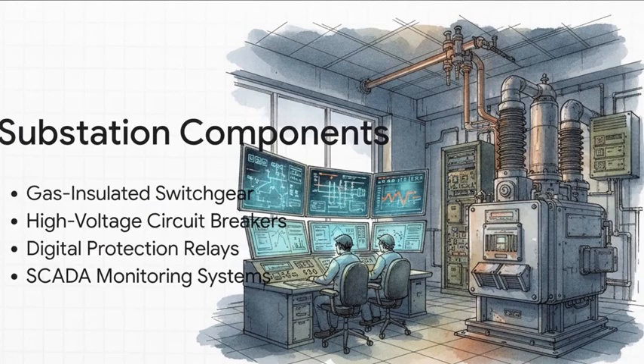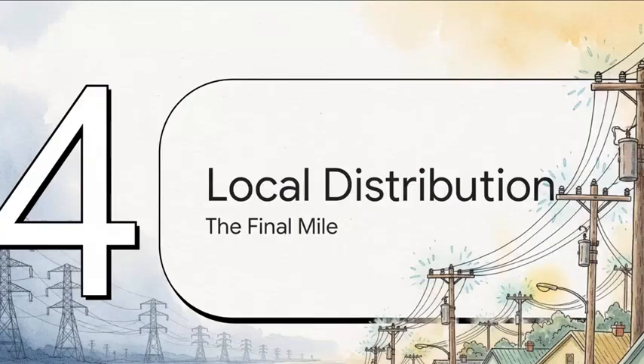But substations do a whole lot more than just step down voltage. They are essentially the protective brains of the electrical grid. They're packed with gas-insulated switchgear, high-voltage circuit breakers, and digital protection relays. These components act in mere milliseconds to isolate faults, like if a tree suddenly falls on a power line, preventing a massive cascading blackout. Meanwhile, advanced SCADA monitoring systems give engineers real-time visibility into the grid's health so they can route power strategically exactly where it's needed.